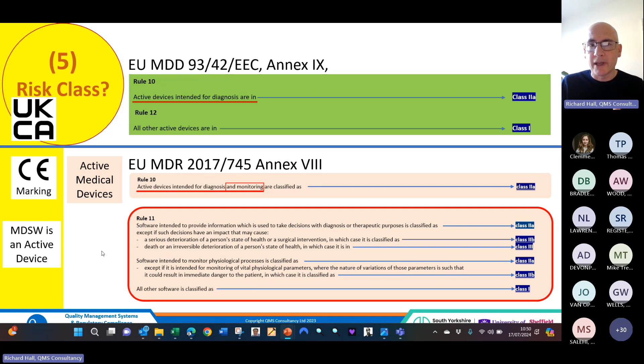It also says software intended to monitor physiological processes is classified as 2A and 2B. And all other software is classified as a class 1. But I can't really think of anything in my career that's not done something captured by these first 2 paragraphs. So it's very likely if you've got software and you're selling the device in Europe or intending to, you'll be at least a class 2A.